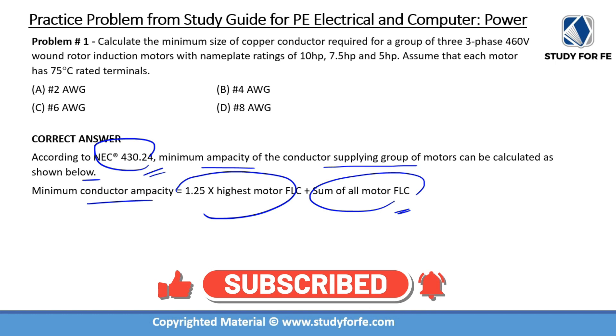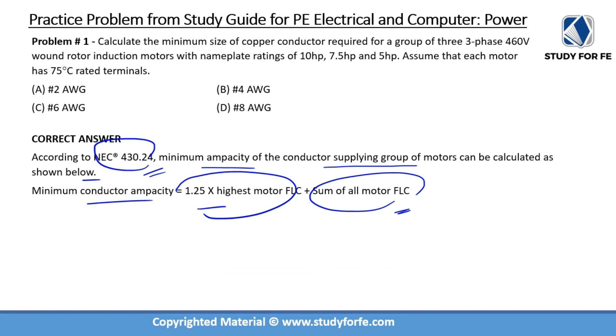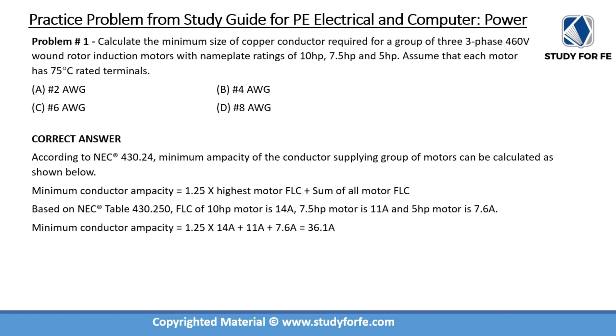As you can see over here, all we need to do is take 1.25 times the highest motor FLC and then simply add the FLC of all the remaining motors. Based on NEC table 430.250 — these are the tables we discussed under part 14 of article 430 — we are dealing with a three-phase application.